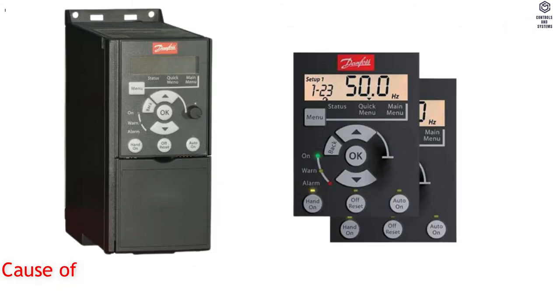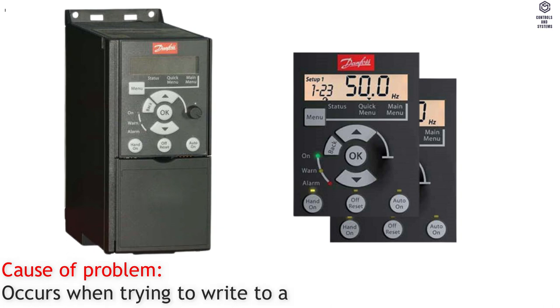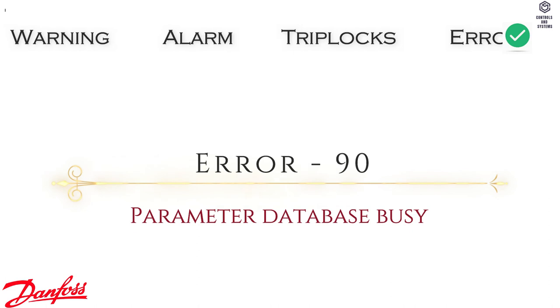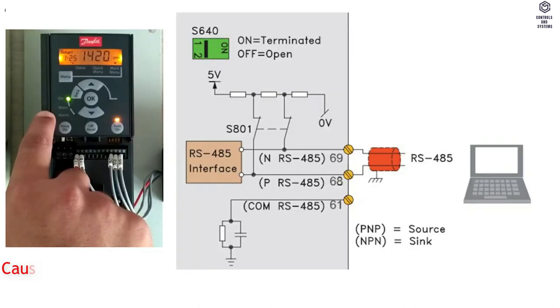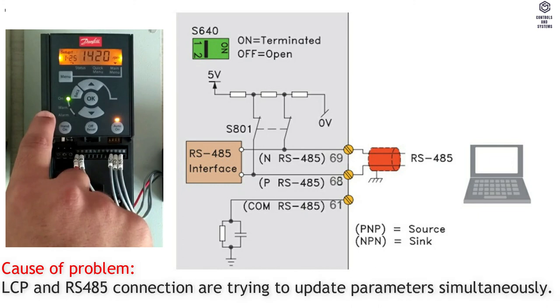Error 89: Parameter Read-Only. Cause of Problem — occurs when trying to write to a read-only parameter. Error 90: Parameter Database Busy. Cause of Problem — LCP and RS-485 connection are trying to update parameters simultaneously.